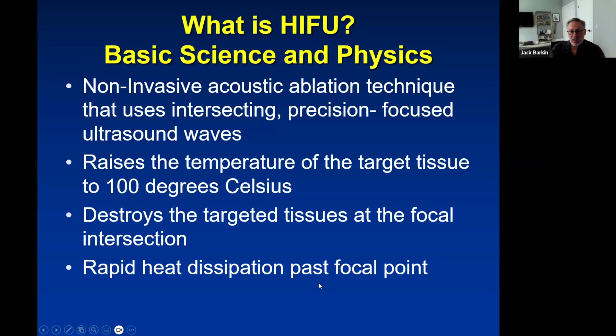And the point is that we're delivering a significant amount of heat energy with acoustic waves, the same ultrasound waves that we use to do your ultrasounds in various areas of the body, but at a different frequency that causes heat to be delivered. But we don't want the heat to go anywhere except to where we are directing it, to prevent other side effects. So high intensity ultrasonic bursts of energy, short bursts, 3-second bursts of energy. And we have determined what energy level should be delivered depending on how far one is from the focal point that you are starting the energy from, and we'll come back to that.